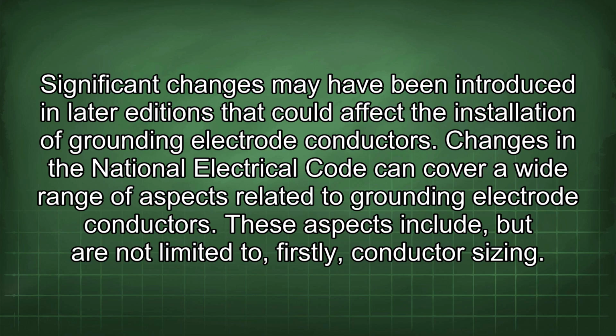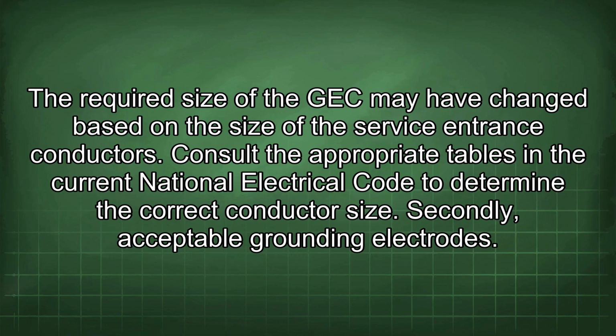Changes in the National Electrical Code can cover a wide range of aspects related to grounding electrode conductors. These aspects include, but are not limited to, firstly, conductor sizing. The required size of the GEC may have changed based on the size of the service entrance conductors. Consult the appropriate tables in the current National Electrical Code to determine the correct conductor size.